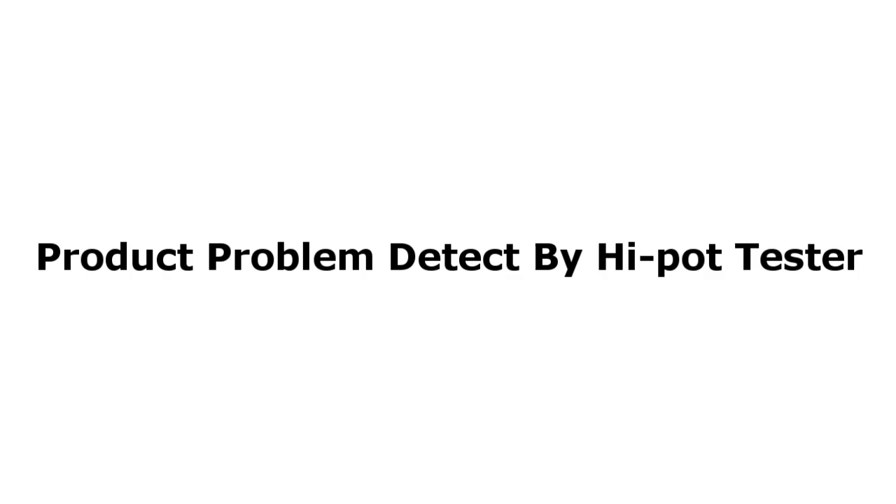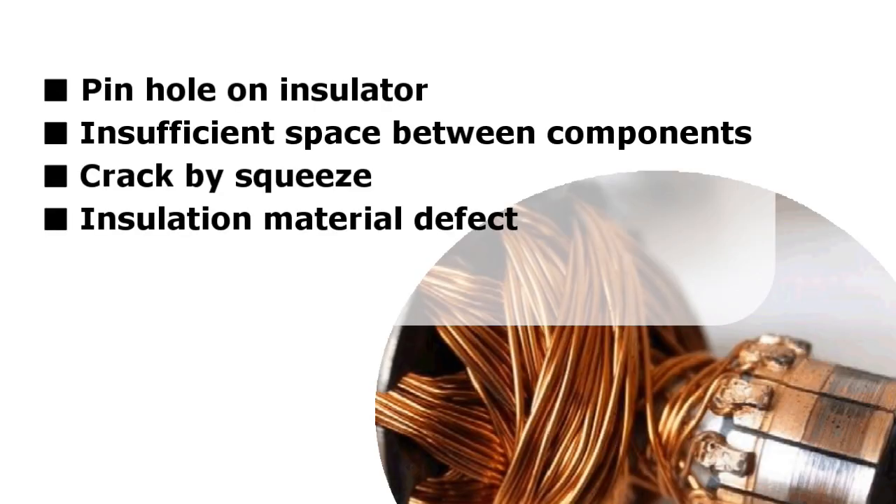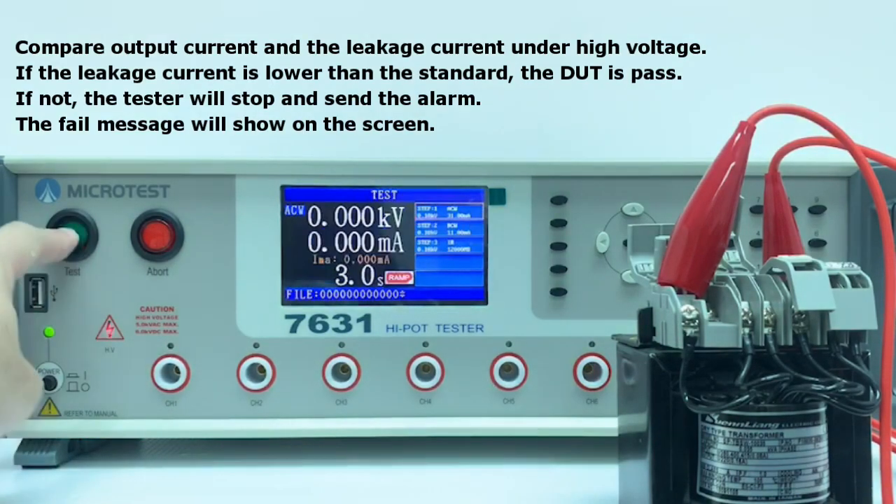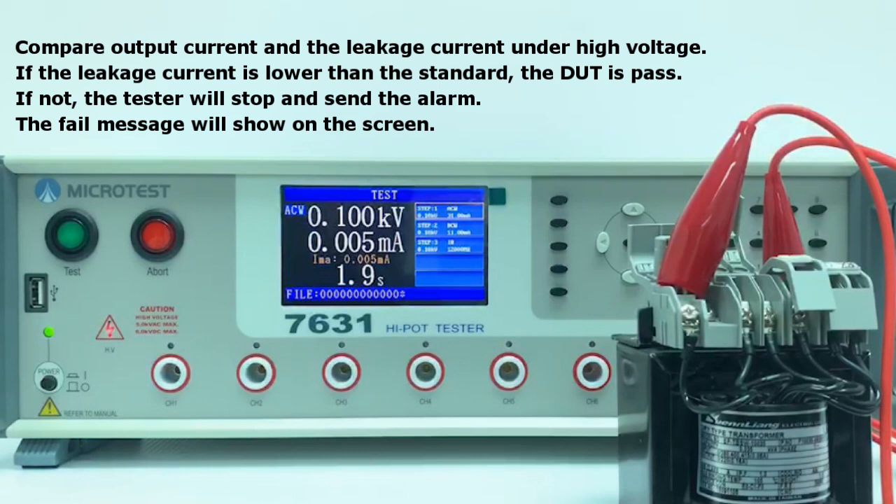Problems detected by the Hi-pot tester include: pinhole on insulator, insufficient space between components, crack by squeeze, and insulation material defect. The tester compares output current and leakage current under high voltage.